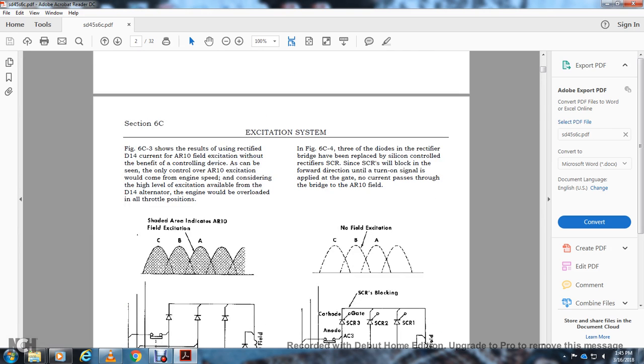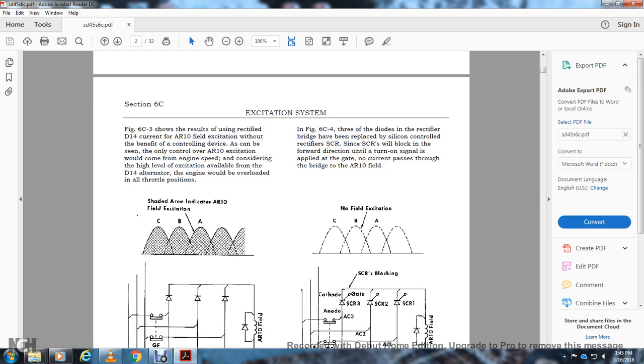In Figure 6C4, the three diodes of the rectifier bridge have been replaced with silicon controlled rectifiers, or SCR. Since the silicon controlled rectifiers will block the forward direction until a turn-on signal is applied at the gate, no current passes through the bridge to the AR10 field.